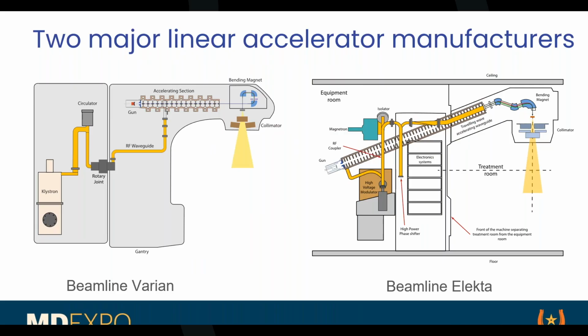Maybe. Which one has the traveling wave? Yes, traveling wave. The traveling wave accelerator is less efficient in how it converts the microwaves to a high voltage, and that's the Elekta machine. Whereas the Varian machine uses the standing wave accelerator, so it's more efficient, and that's why the waveguides are shorter. And the way that the Elekta machine is lowered, this line over here is what we call isocentric. That's the line that the machine rotates over, and it's lower than the Varian machine.